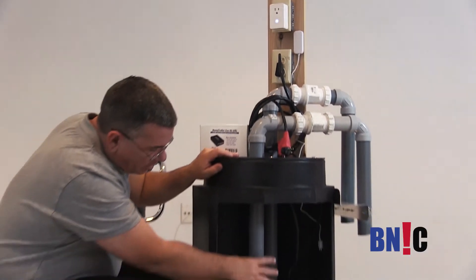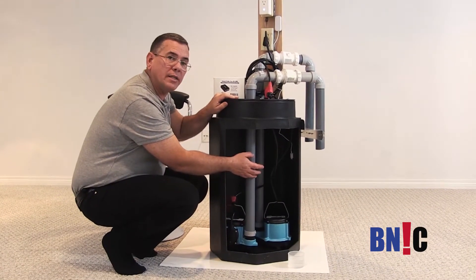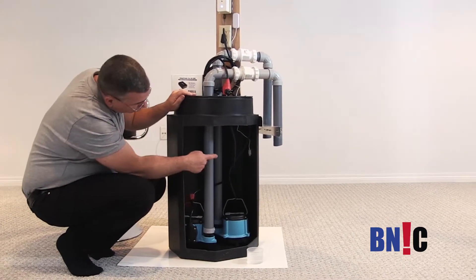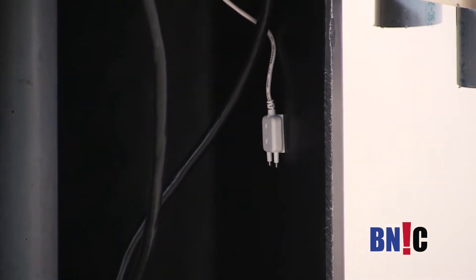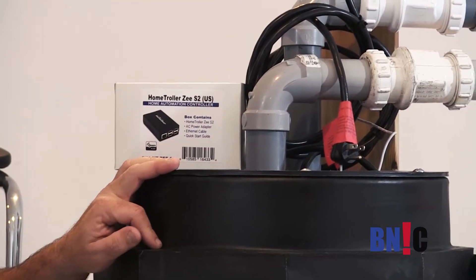Now, if the main pump fails and the water inside the pit rises over the normal operation level, the water is going to close the contact on the probe. And the probe is going to send a signal to the HomeTroller, and the HomeTroller is going to tell the power outlet to turn on.